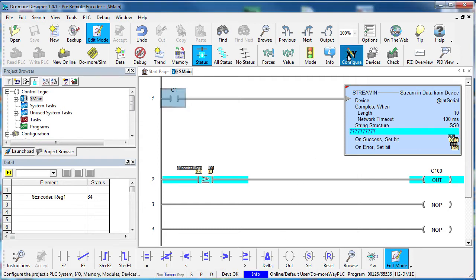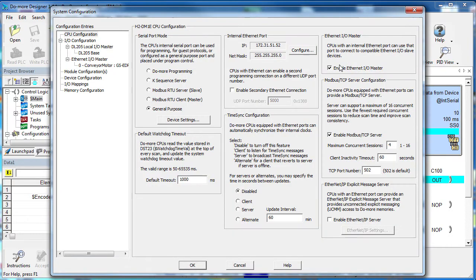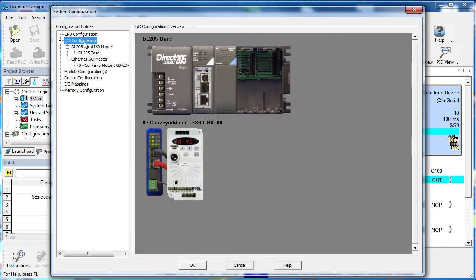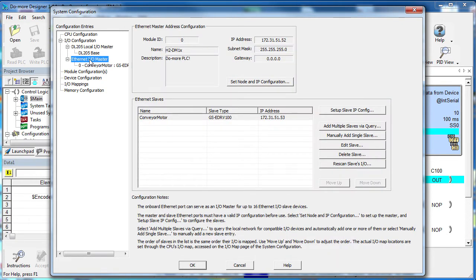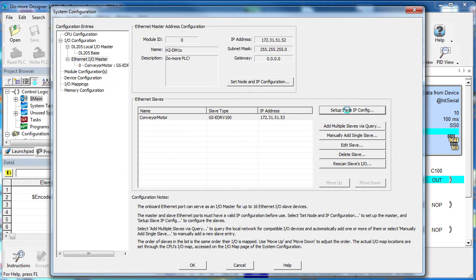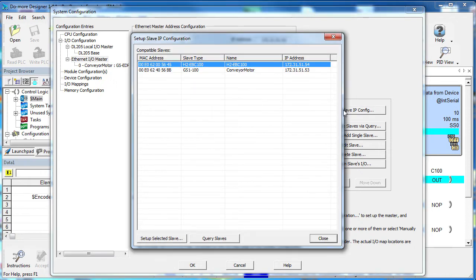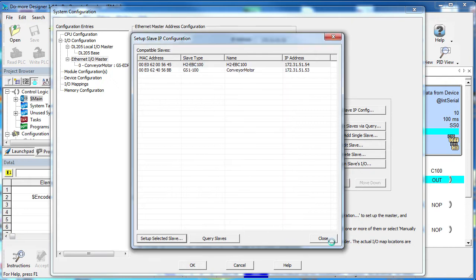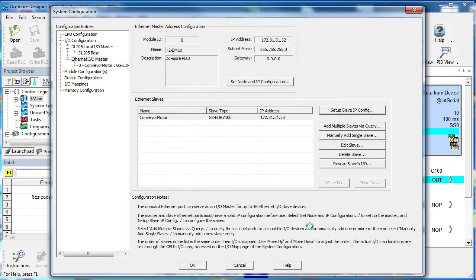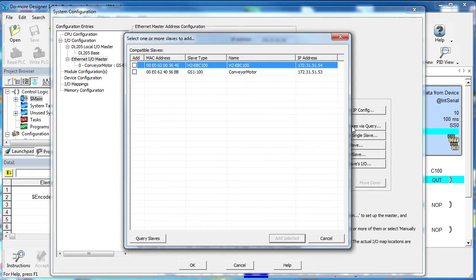So, we go to the system configuration and just like always, we start at the top and work our way down. There is no change to the CPU. We did change the I-O configuration. We removed an entire local module from the local base, right? To add the remote slave, we go to our Ethernet I-O master because he manages all our slaves. And before we do anything, we need to hit this button to make sure all the IP addresses are OK. Looks like our slave's IP address is good, but if it wasn't we would just change it here. Now that we know that all the slaves we want to talk to are on our network, we hit this button to add them to the configuration list.